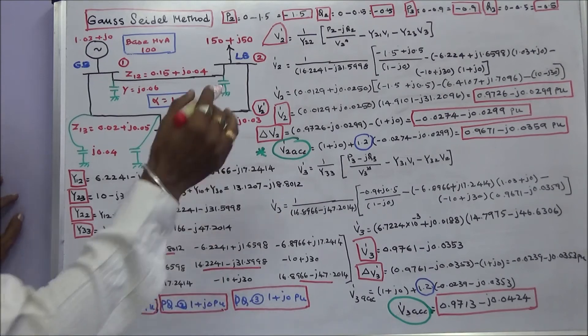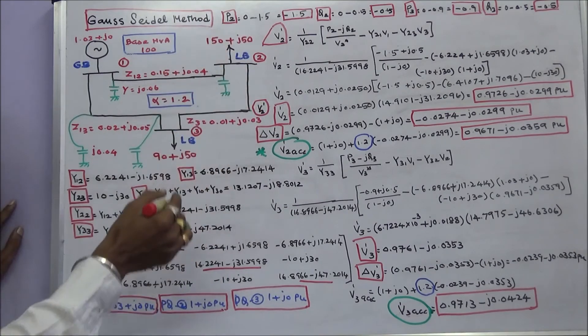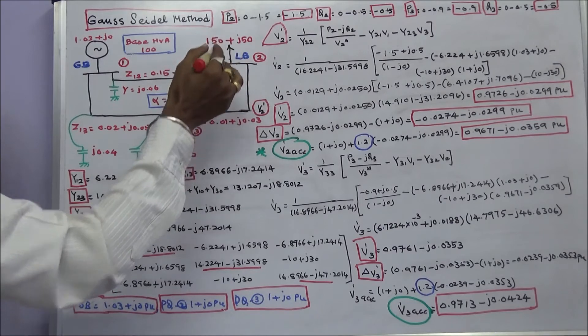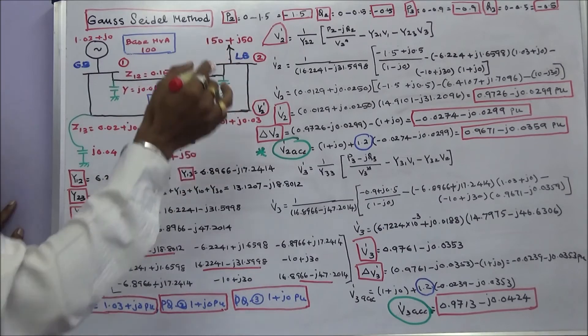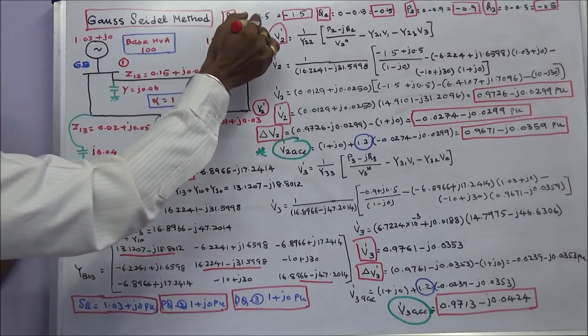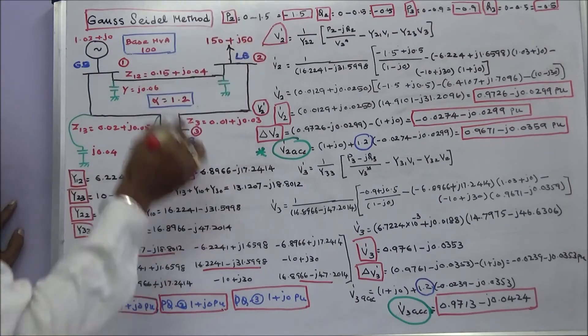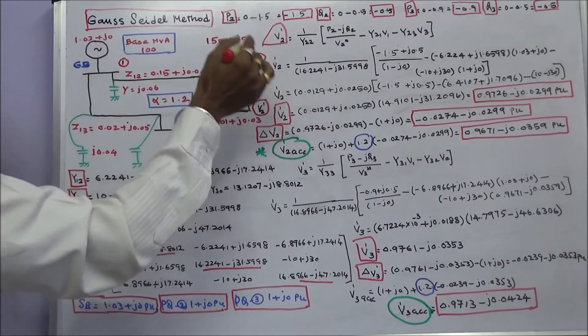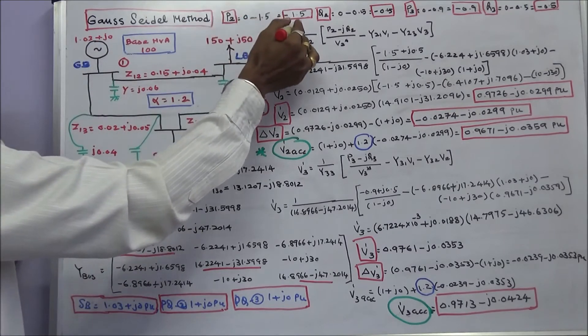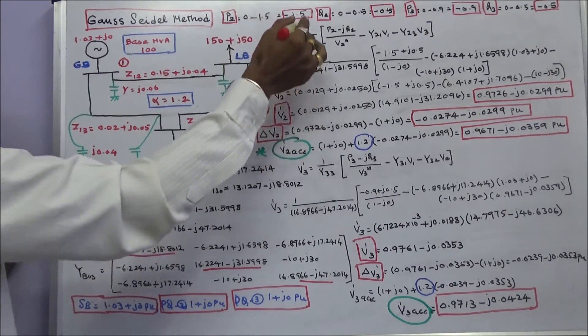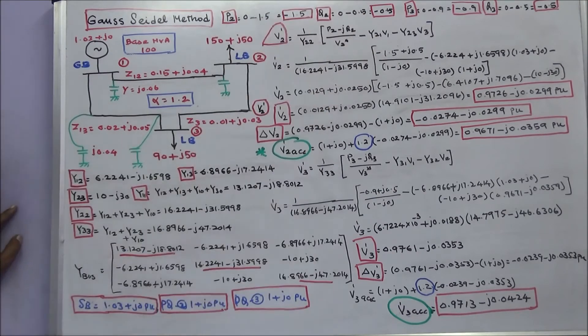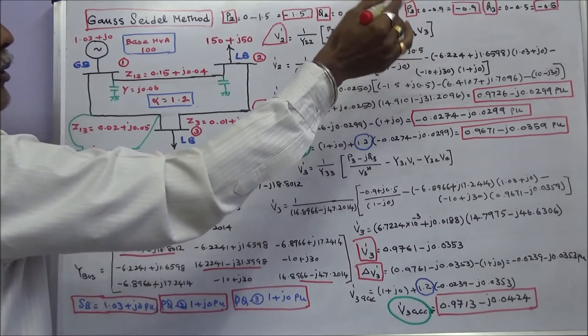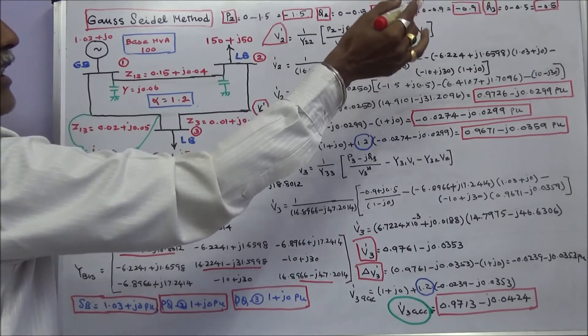Next we calculate P2. Power generation at the load bus is 0, so P2 = 0 minus 1.5 (since the base MVA is 100 and load is 150 MW), giving P2 = minus 1.5. Q2 = minus 0.5. Similarly, P3 = minus 0.9 and Q3 = minus 0.5.